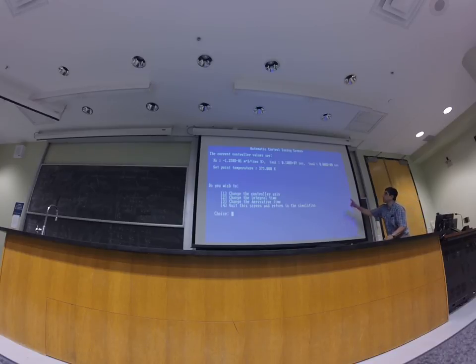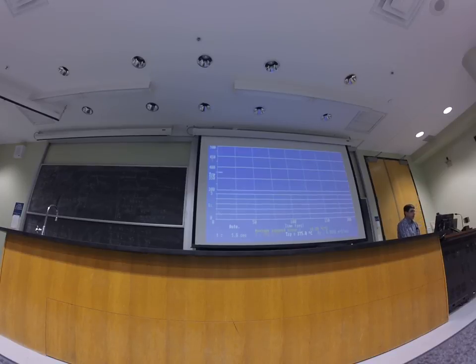Tau derivative is 0, so we leave it at 0. So to eliminate integral action, I put tau I something ridiculously large. And notice tau D, the derivative time constant, is indeed 0. So let's see how I do. One thing is that it's aggressive, so you can see that the manipulated variable tends to move too much. That's not good for control valves.